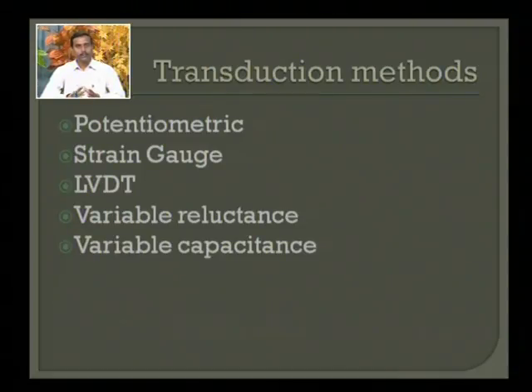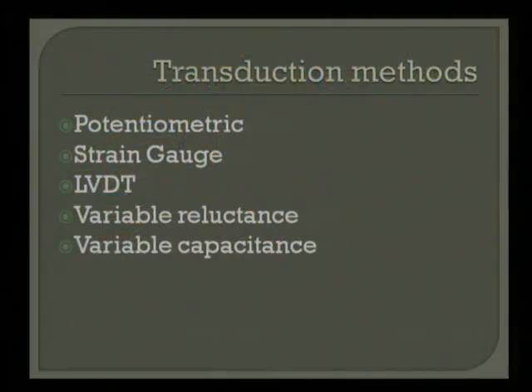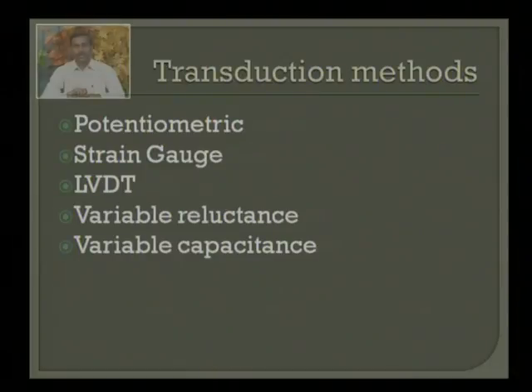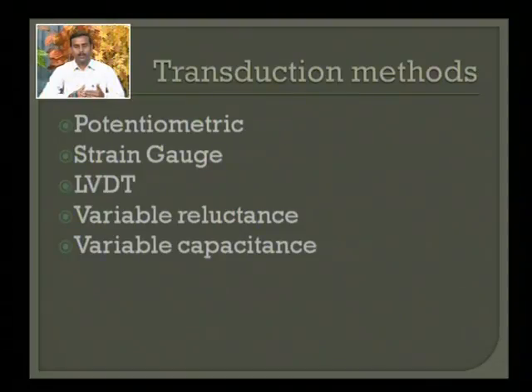If a scale is placed at the top of a particular diaphragm or bellow, with vertical lines marked with pressure values, that scale can be utilized for measurement of pressure. Alternatively, a rack-and-pinion arrangement converts linear displacement to angular displacement, which can be marked on a semicircular scale. For transduction of displacement to an electrical quantity, the potentiometric method can be used: the displacement from the pressure transducer is connected to a potentiometer, and the voltage drop across the lower part is proportional to the angular or linear displacement.